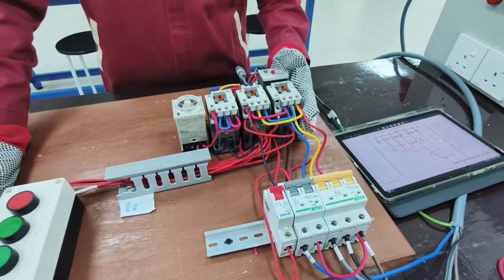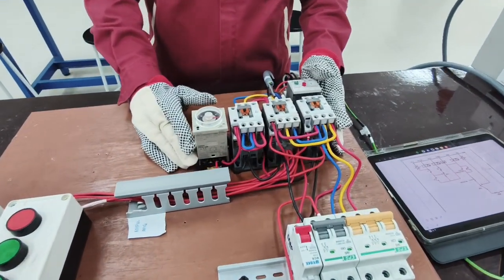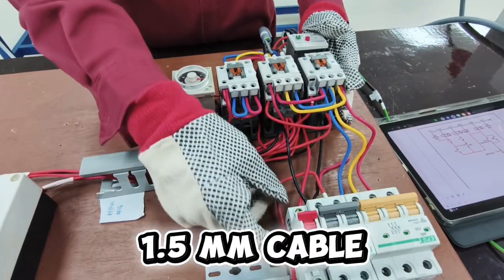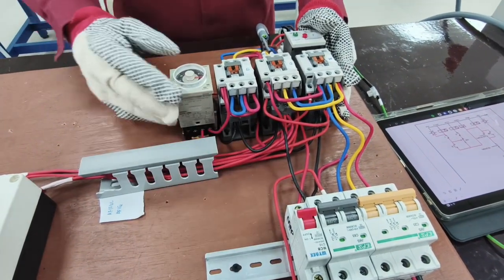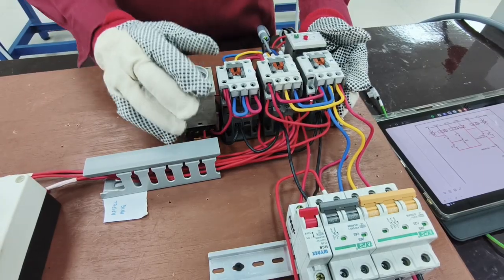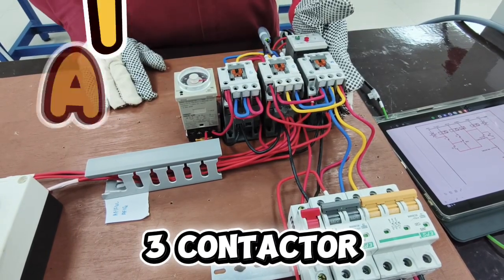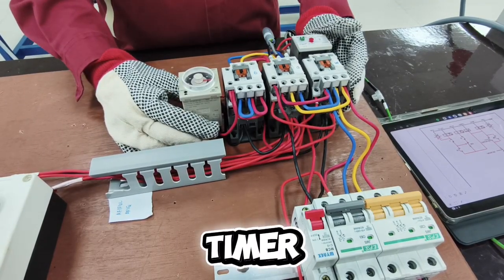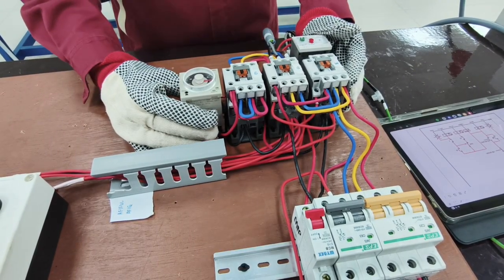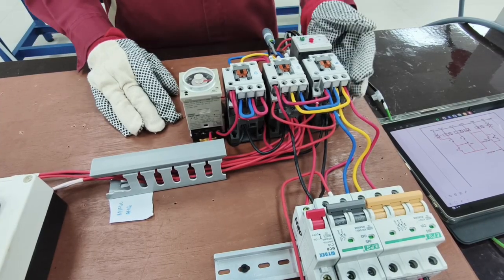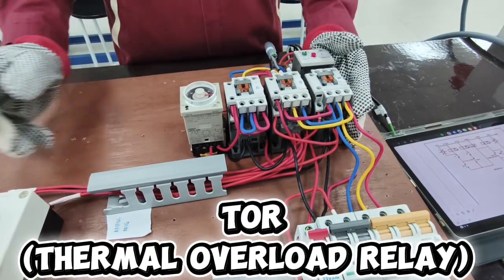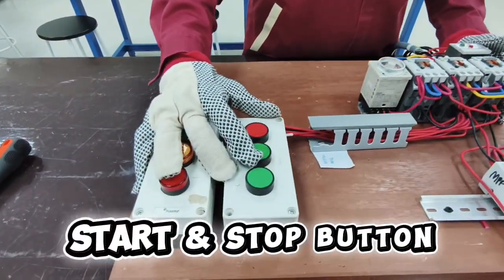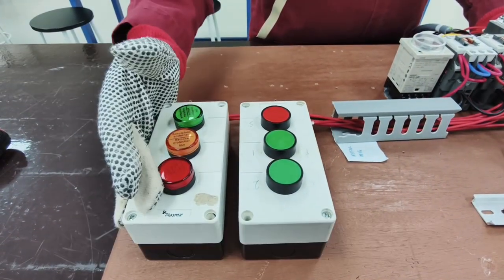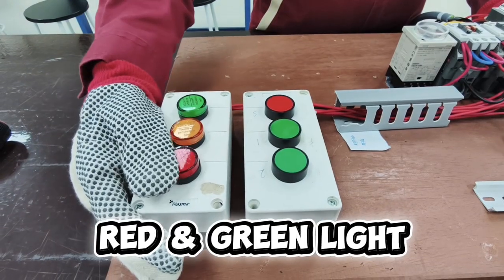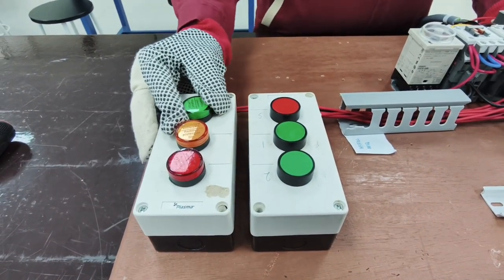Okay, so for the control circuit, we have 1.5 mm cable which supplies the single phase current to the three of our contactors: the main contactor, delta contactor and star contactor. We also have a timer, the Omron H3CR timer, and we are also using a TOR. We also have one start button and stop button, and two indicator lights, red for trip and green for running motor.